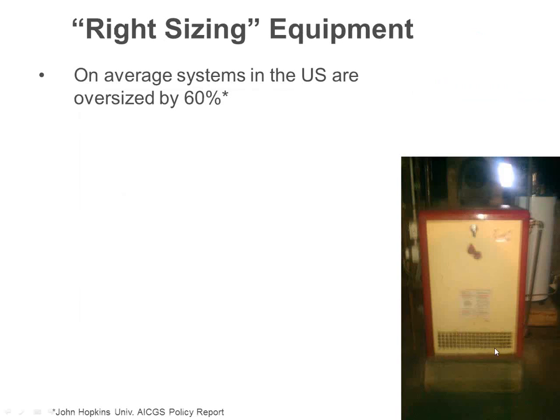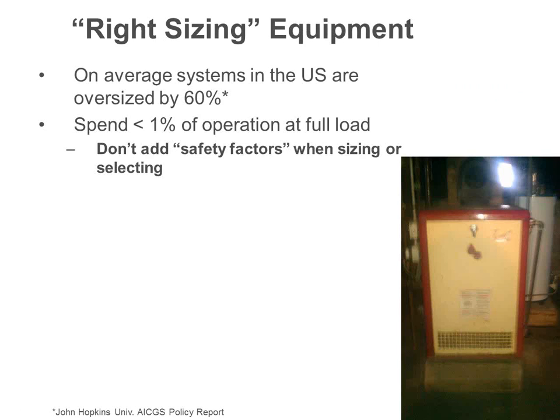So now 30 years later, somebody else goes in and just looks at that tag. And the wholesaler has another special deal. So this is what just keeps happening and happening and happening. That little boiler on the right over there is probably about 40 years old. I actually did a radiation count in that residence. The total connected load was about 78,000 BTUs. That boiler itself is 198,000 BTU input. If you don't think that thing cycles, you just hear it.